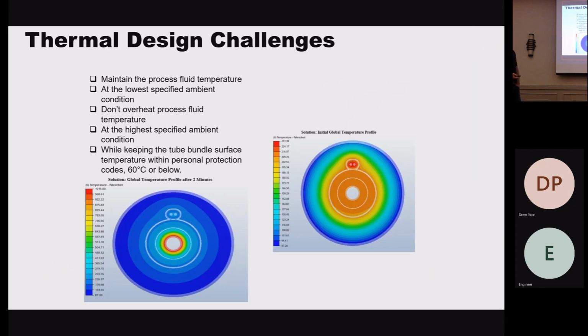All right, getting into design. You guys heard this yesterday. We're looking at the maintained temperature while looking at the lowest ambient temperature. We also don't want to overheat the fluid and make sure we're not getting that outer jacket temperature above a touch safe of 140 degrees F. So those are the things we look at from an overall standpoint.